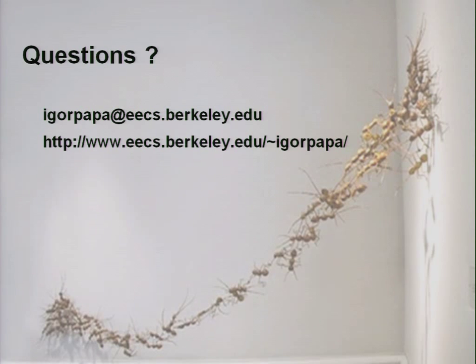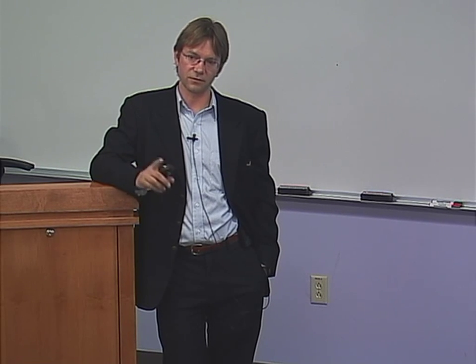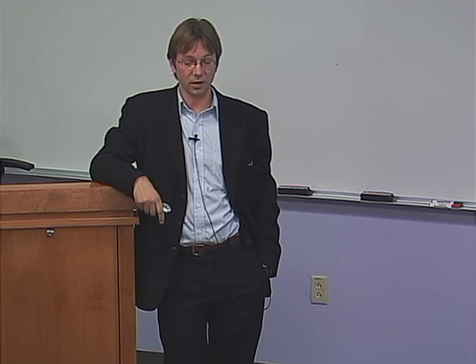For the underground cable case, have the utility companies given you any guidelines for how far apart you can do your measurements or how close together you can do them? Right. So they gave us a target spec of 300 feet. They would like to see us being able to detect a fault at 300 feet from the fault site. And we are able to do that.